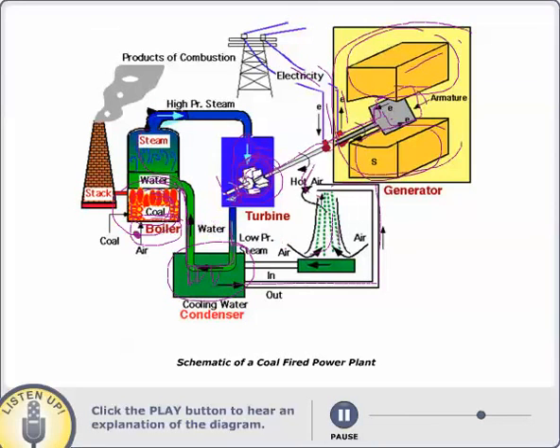Basically, almost about 30 to 40% of the energy that we put into this device is actually dumped out into the environment through this condenser or cooling tower. That is the reason this turbine part is notoriously inefficient. The boiler part is pretty good, actually—it's about 90% efficient. This is about 40% efficient.